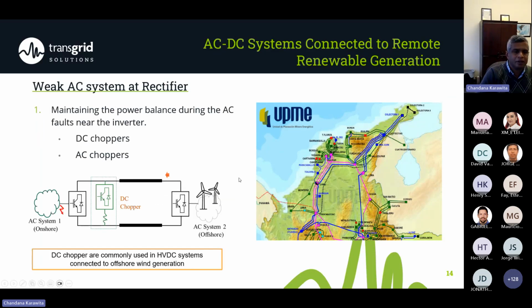Another requirement is this: let's say we have a fault on the inverter side. That is kind of a load rejection for these wind farms or solar farms, so we need some way to absorb the energy during faults on the inverter side. Right now, for offshore systems connected through HVDC links, we use DC choppers for this purpose. You add a DC chopper to the HVDC, and during a fault on the inverter side you operate the DC chopper and absorb the energy coming from the offshore system, so the system stability is preserved. This is the common way of doing it for offshore systems.